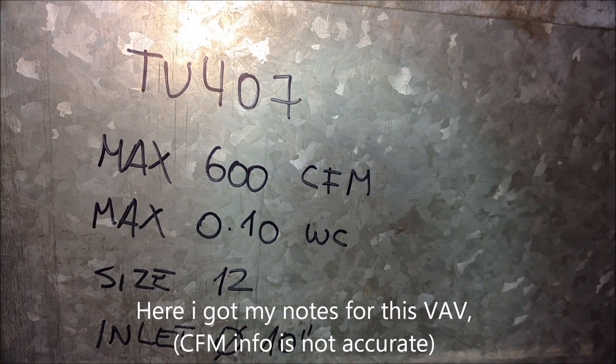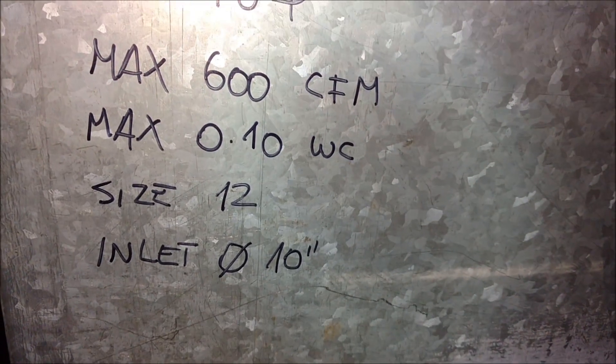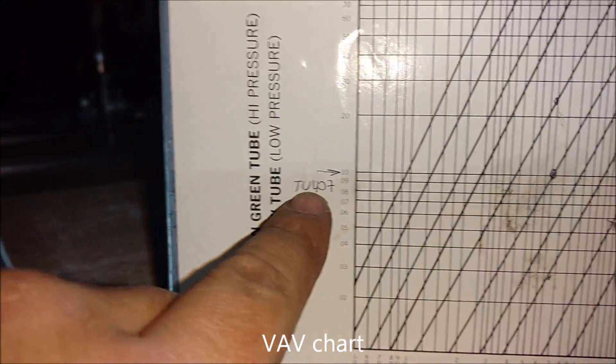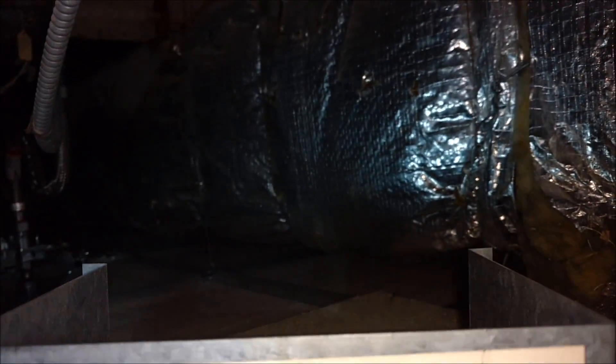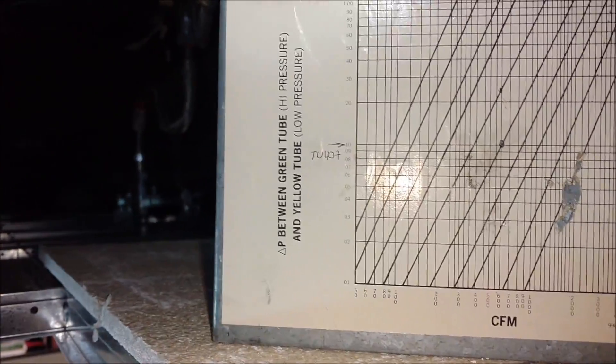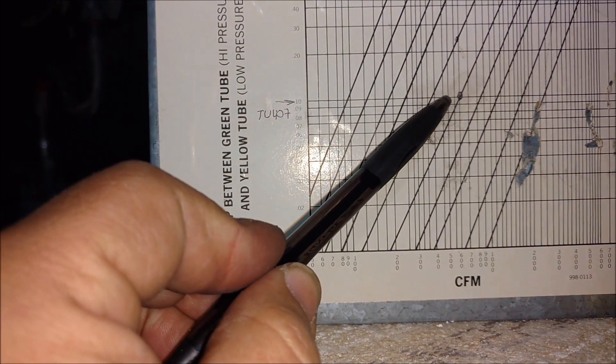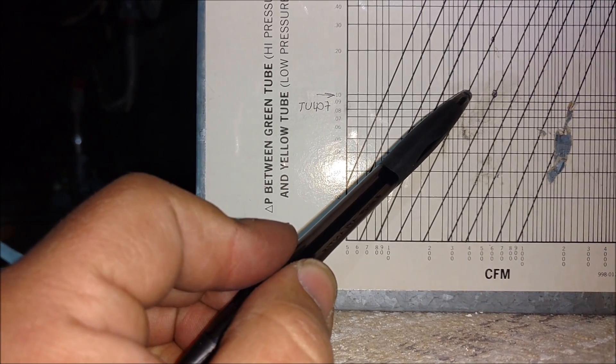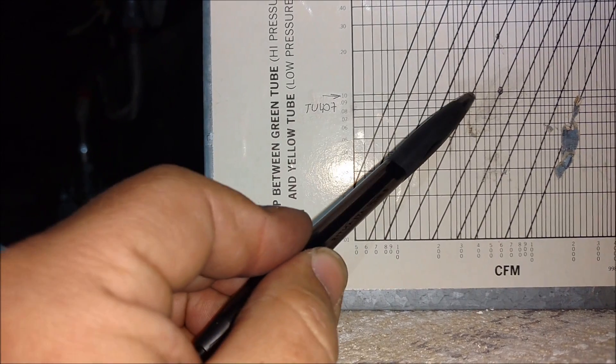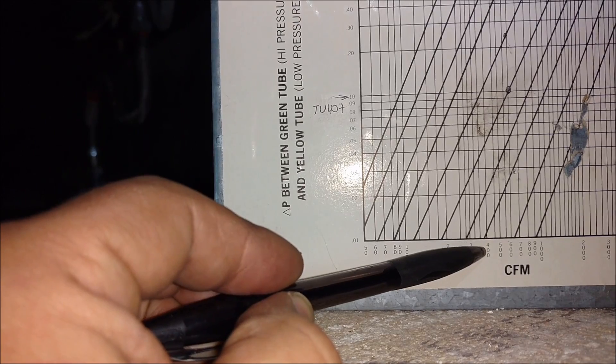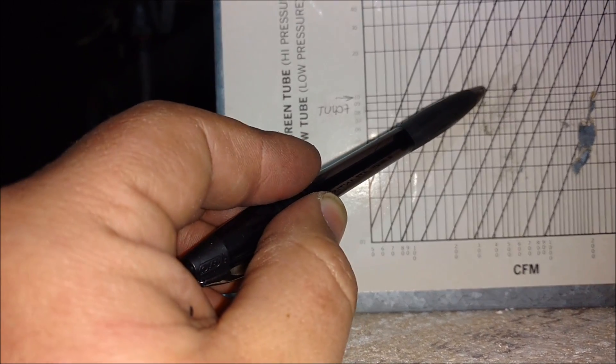My VAV is a TU-407. This is the information regarding this VAV. The controller comes with a little chart. For my VAV, the inlet is 10 and the size of the box is 12. So we should have 350 CFM maximum for that VAV.